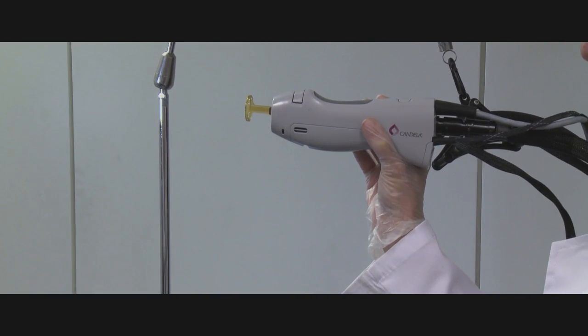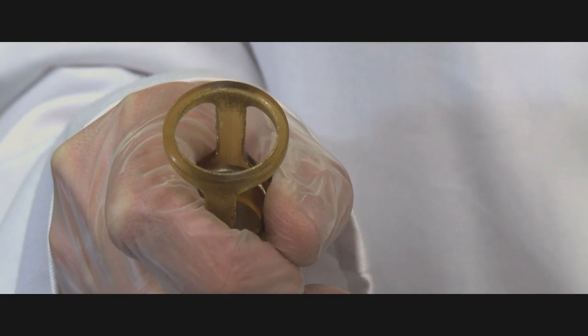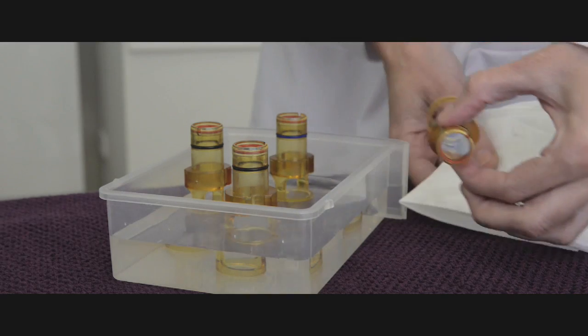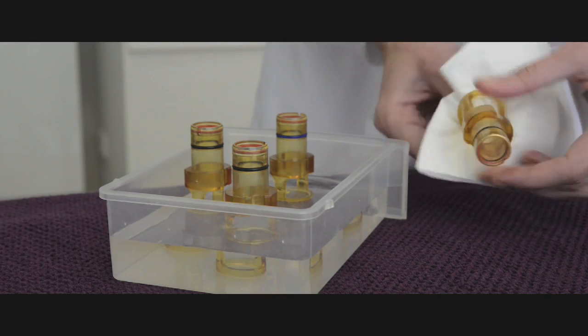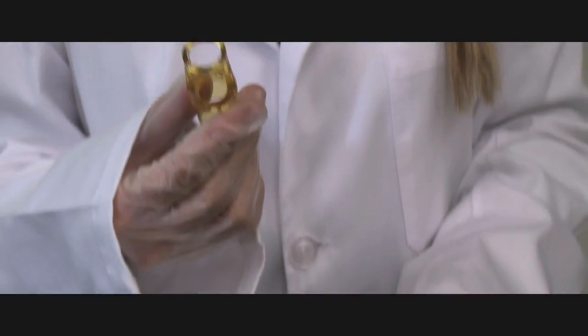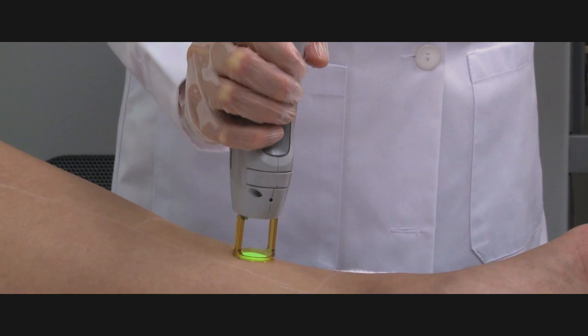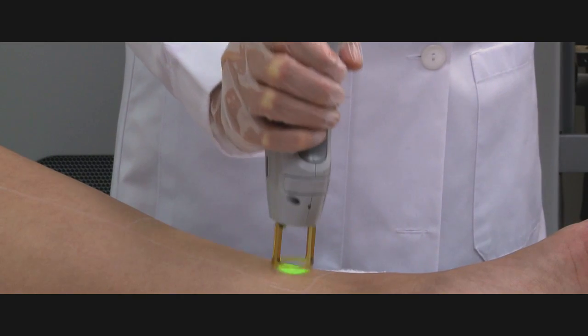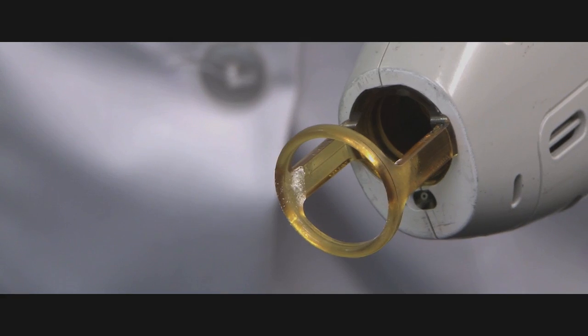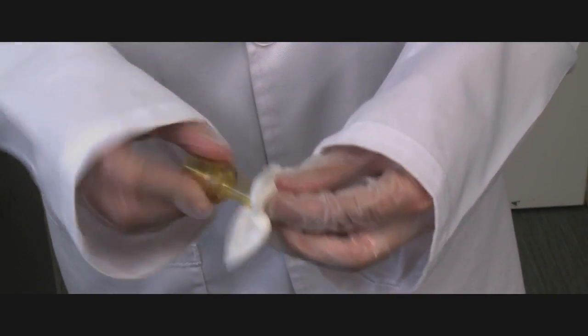Make sure your distance gauge is clean and has no black stain on it. If it is developing black stains, you may clean the end with a diluted bleach solution. Change your distance gauge every 200 to 300 pulses — a clean window and fresh gauge can be quickly and easily attached. Also during the treatment, keep the distance gauge free of any frost from the cryogen by quickly wiping every 30 to 40 pulses. And of course, clean with isopropyl alcohol or medical wipes between patients.